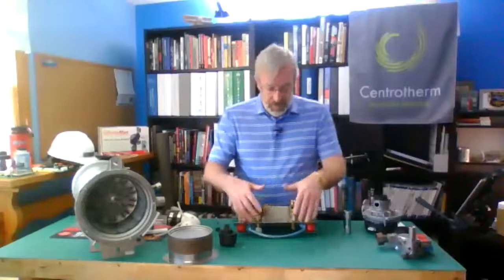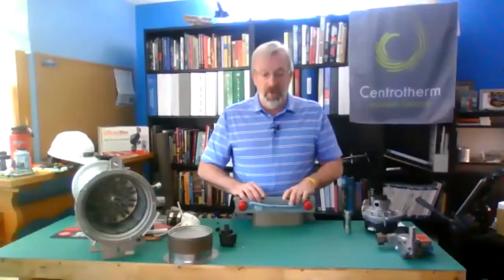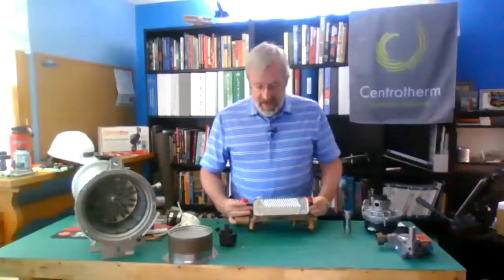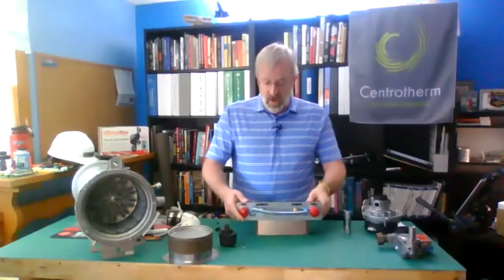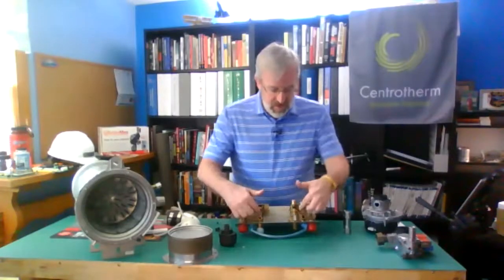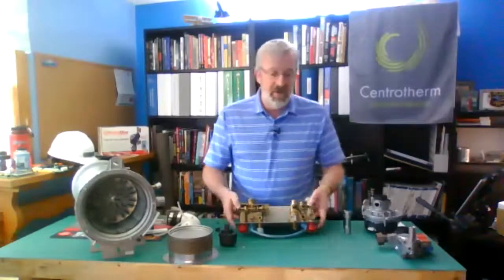Now, if you want to flush this and you did not put a set of service valves, or I'm sure everybody that's on here would put a set of service valves in if they were putting one in, but let's just say somebody before you didn't do it. So what we have is you can take this whole thing off without a whole lot of work. There are 2 screws right here on the front. So there's 2 4mm Allen screws. Take those out. This has got a set of O-rings on it when I pull that out. Now you have the entire brazed plate heat exchanger in your hand.